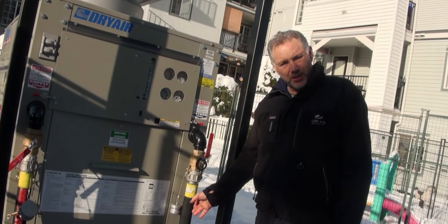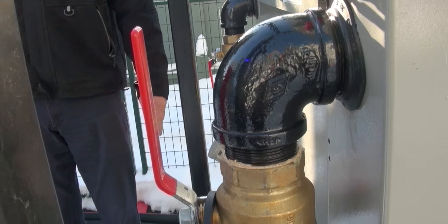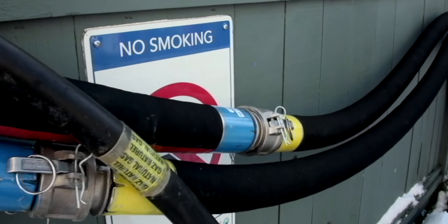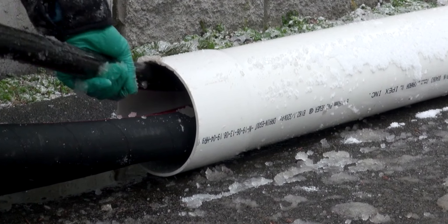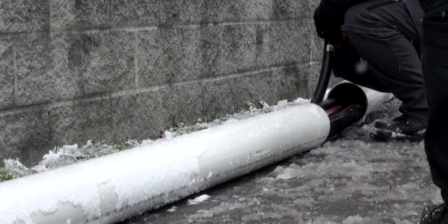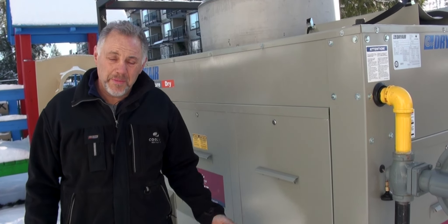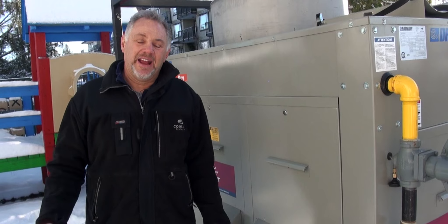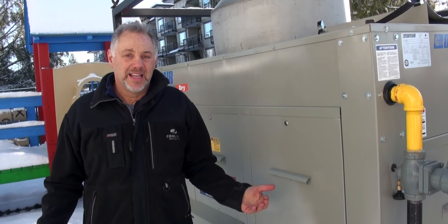These are high-pressure hydronic water hoses that carry the water to and from the building that we're heating. We've encased them in plastic piping in the lane to prevent damage — vandalism, a car hitting them — and also to protect them from the snow and ice conditions we're experiencing right now. This boiler utilizes a natural gas feed from the building. We also get electrical that energizes our pumps to help us distribute the hot water we're making, and ultimately it gets into every single suite through the radiators in the rooms to keep the families that live here comfortable.